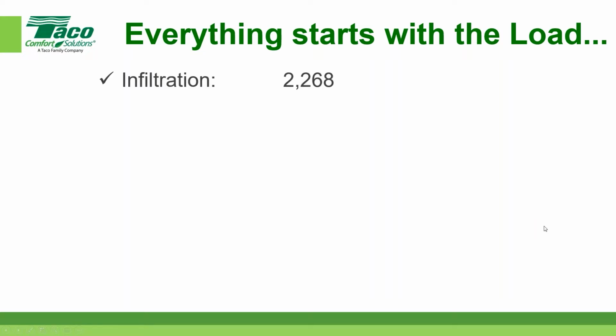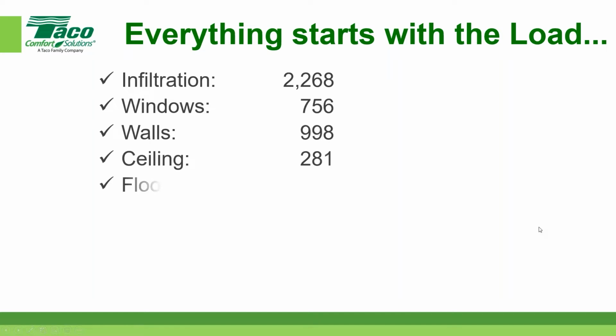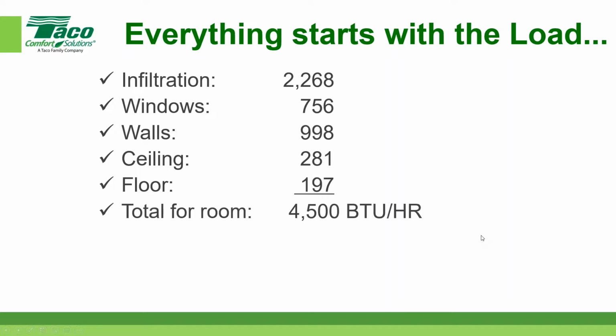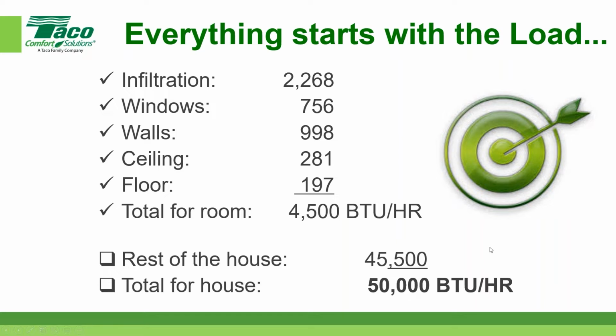Here's just an idea of what one of those heat losses might look like. We start with a room by room heat loss. We got the infiltration, we got windows, walls, ceilings, we got doors, things like that. Finally, the floor. And we're in seminar land, so we make our numbers nice and round. But let's say this one room is 4,500 BTUs an hour. Then we do the other rooms in the house for a total of 50,000 BTUs. That's going to be our bullseye on our target. That's what we're shooting for. So anyway, just understand this is a fundamental starting point of everything that we do in the world of heating or cooling or anything. We need to know what the load is.